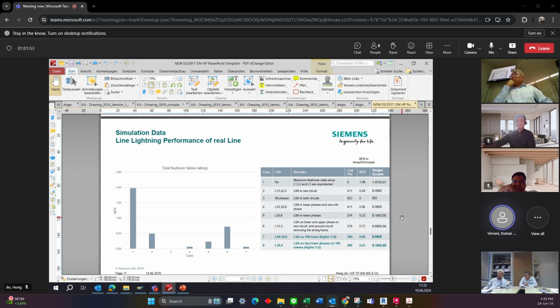On the top there is a shielding wire we will install. Because of the shielding wire, it will somehow protect the top phase and the middle phase, but there will not be a major protection for the bottom phase against back flashover. So it might be required that for some towers we need to install the arresters on both the bottom phases.